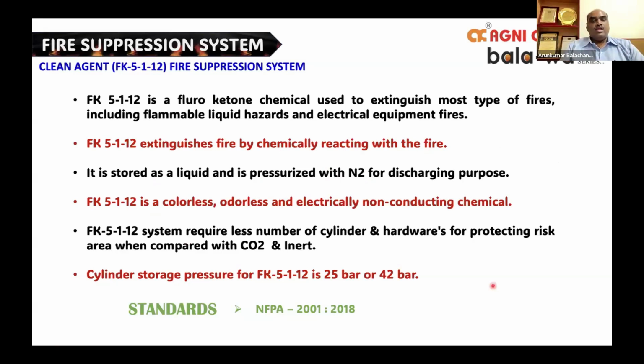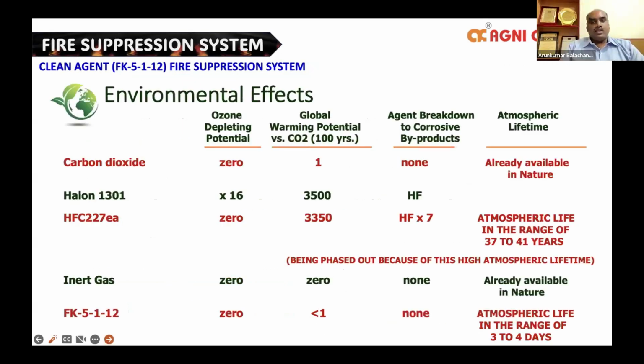When an FK system is used, the number of cylinders and hardware for protecting the risk area is very small compared with a carbon dioxide or an inert system. The nitrogen pressurization can be with either a 25 bar system or a 42 bar system. Again, we'll go into the environmental effect of the FK system. For FK, the ozone depletion is 0. There is a small global warming potential, but it is less than 1.